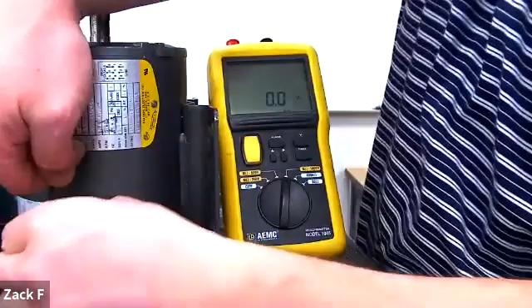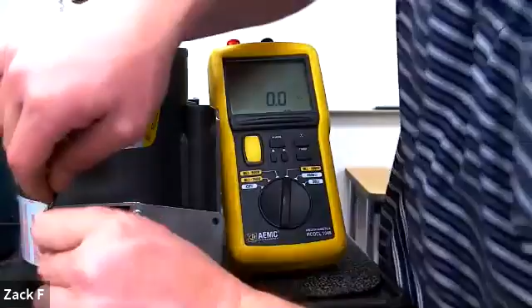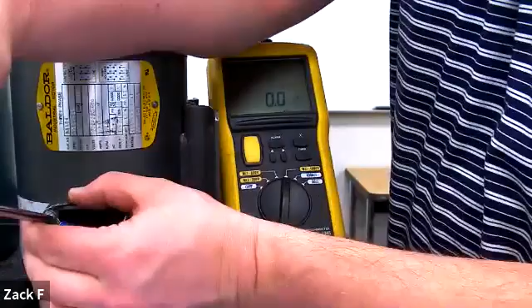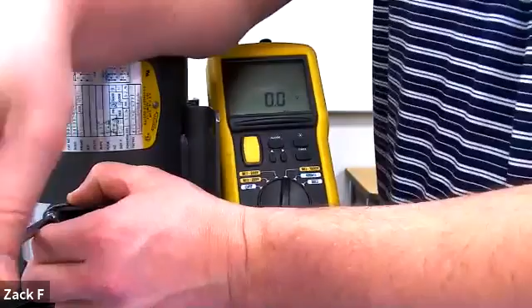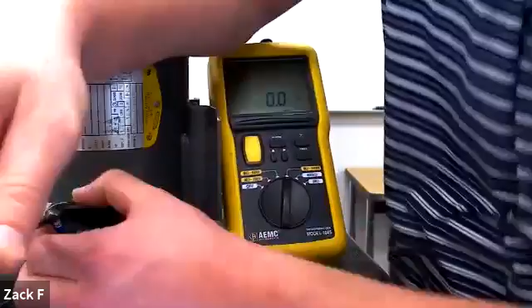You asked about rule of thumb earlier too. You might see this, or you could use it on the lab. The rule of thumb for these readings is 2 megohms. You'd use that at work too. If you see something under 2 megohms, that's a lot of ohms, that's bad juju. At that point it will probably continue to get worse and worse until it just fails.